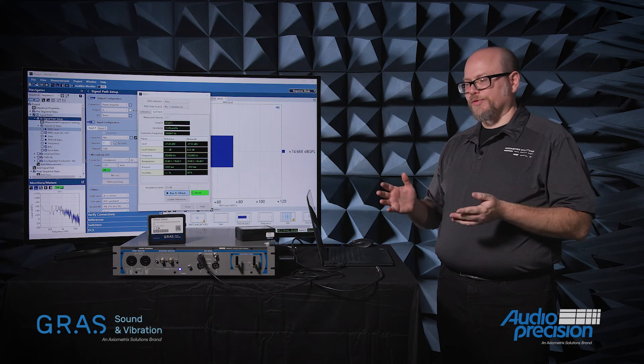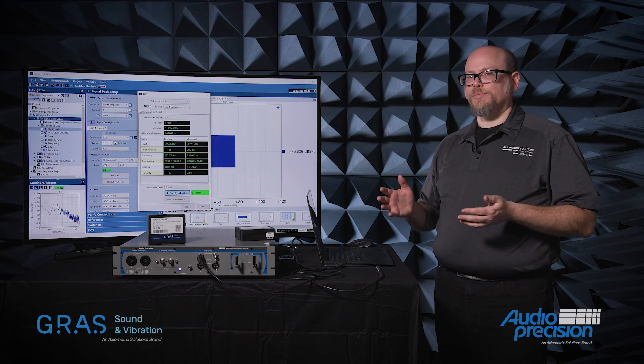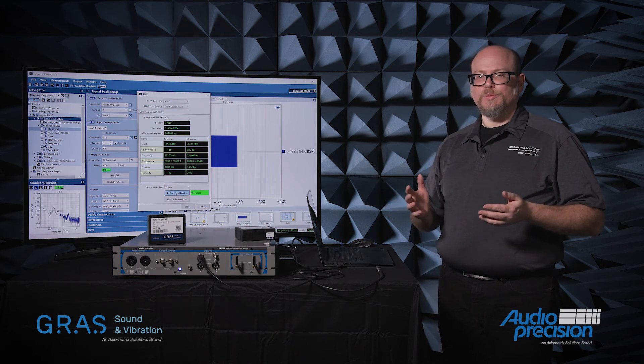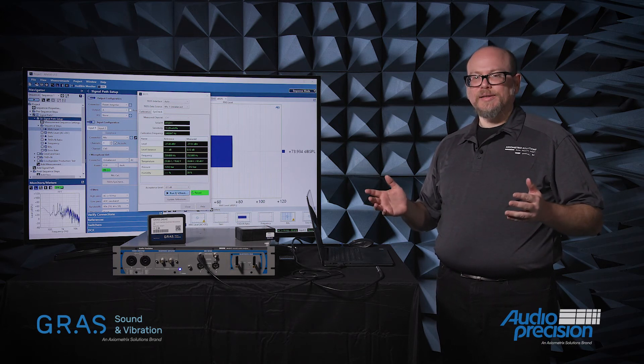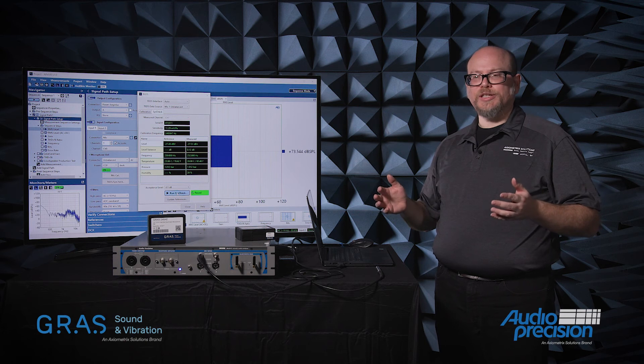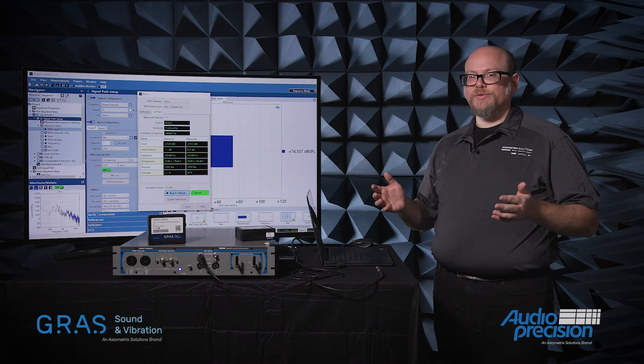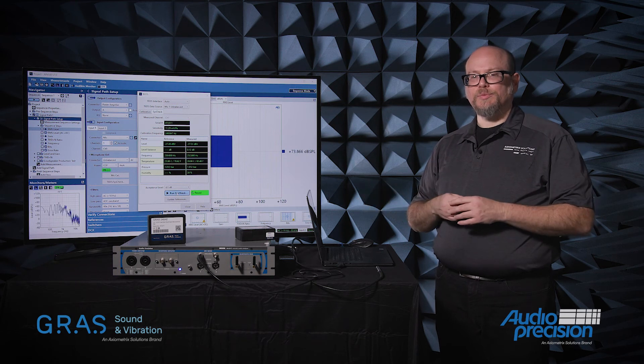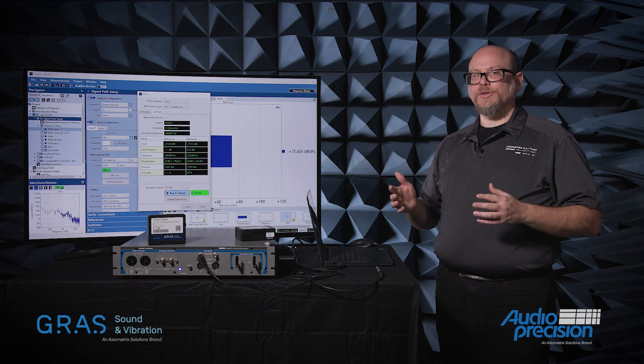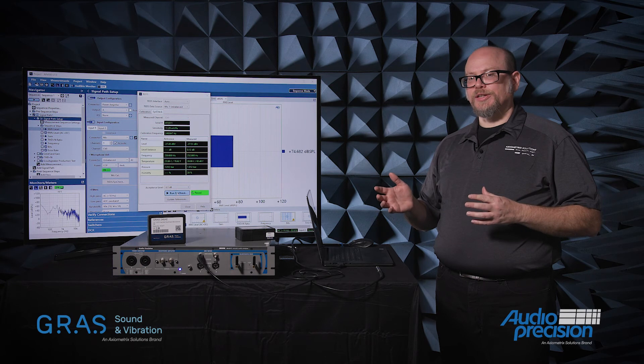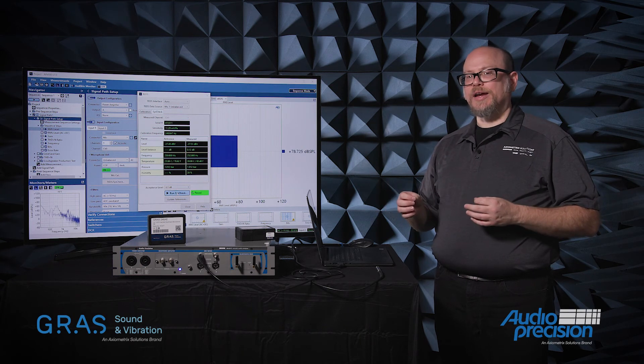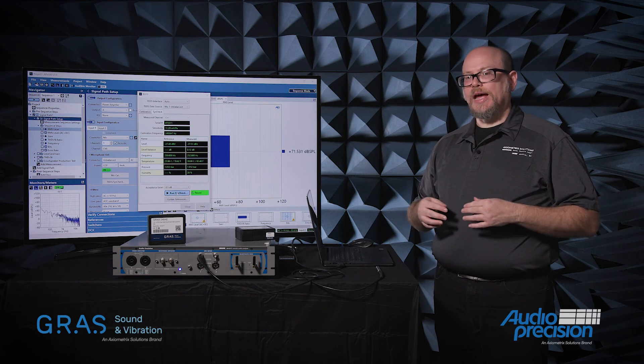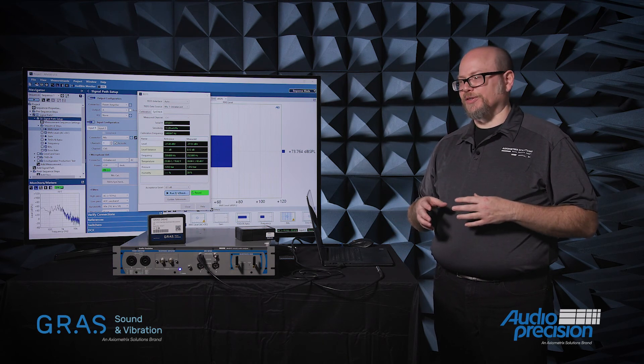And of course, the virtue of this is that potentially this microphone is not in a place that's easily accessible to me. Perhaps it's installed in an array, or in a test fixture in a production environment, or just inside of a large chamber, and you're standing outside of the chamber where the computer is located. In all those situations, SysCheck 2 allows us to verify the accuracy of the entire signal chain without having to have physical access to it.